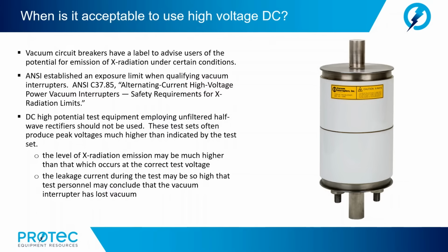A bad interrupter filled with air will have a similar high leakage current in both polarities. A good interrupter with a good vacuum level may still have a high leakage current, but this will generally be in only one polarity. Such an interrupter usually has a tiny sharp spot on one contact that produces a high field emission current when the sharp spot is a cathode, but not as an anode. In addition, such an interrupter would also normally withstand the required AC voltage, which is the definitive test of its vacuum integrity.